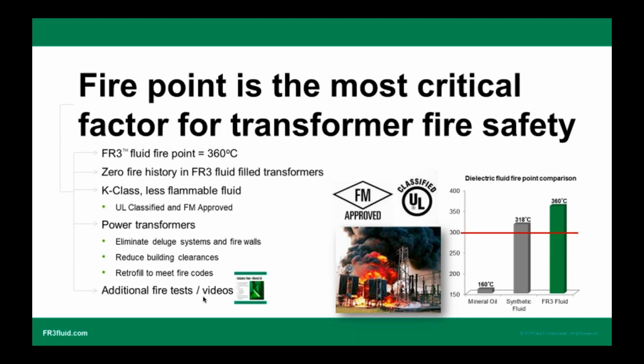A lot of people always have a question in mind: my transformer is ONAN. That ONAN has nothing to do with the oil. That ONAN means it has a coolant or dielectric fluid inside, which is O-class. It has nothing to do with the mineral oil. In the same way, if you have a transformer filled with a K-class fluid, the transformer becomes KNAN. This KNAN is nothing but a fluid which has a fire point of more than 300 degrees C.